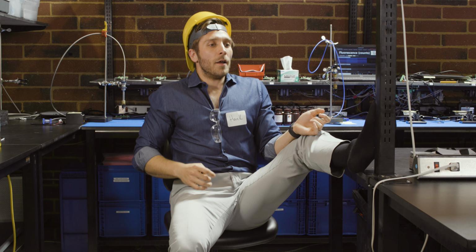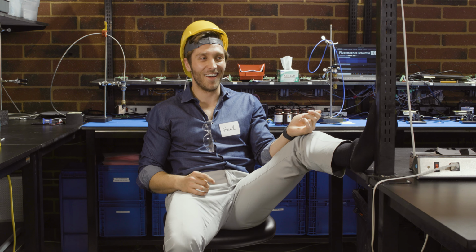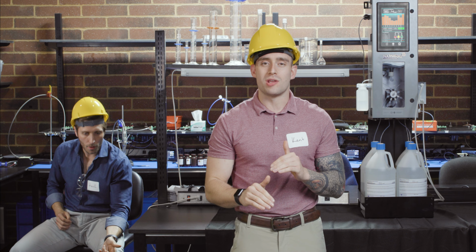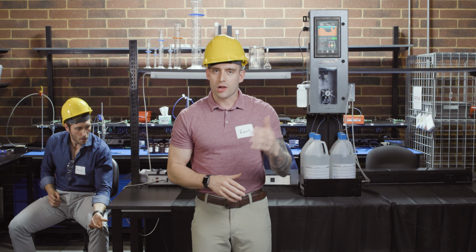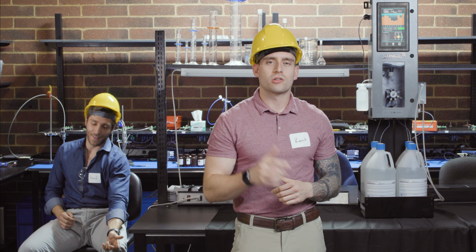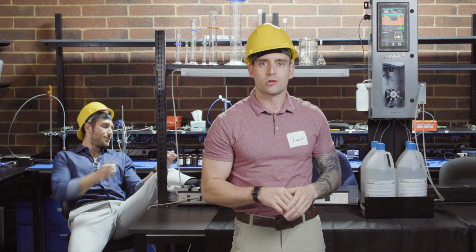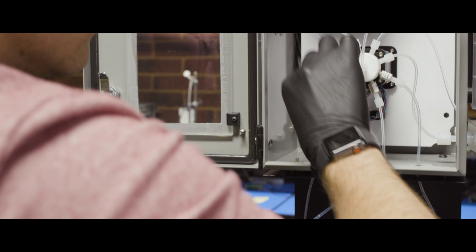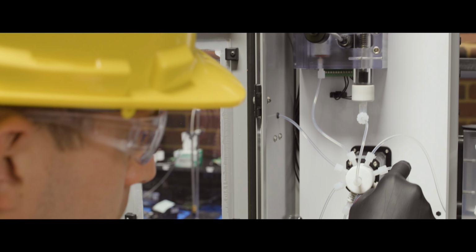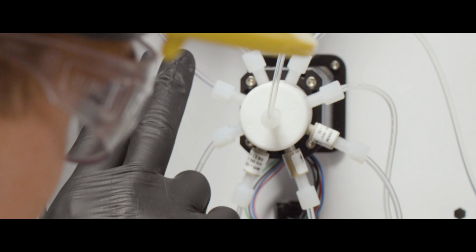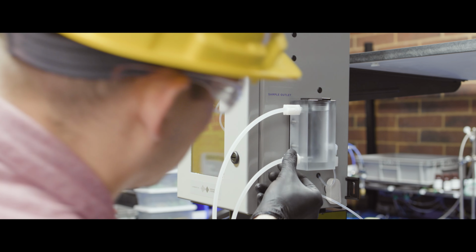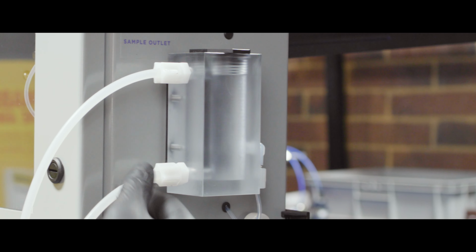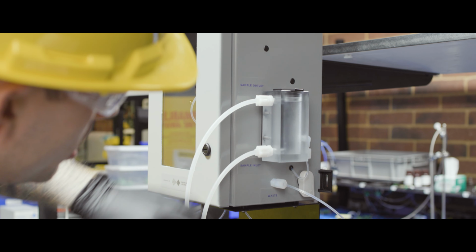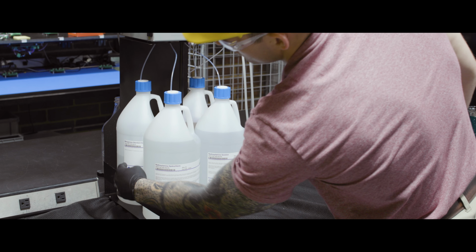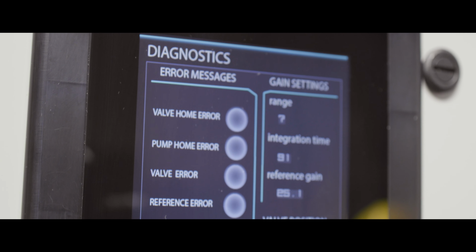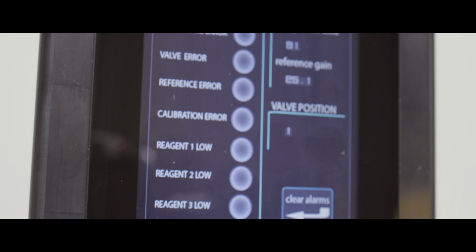Dude, listen. Kenny Ken. So, the Narwhal was designed to ensure that we keep maintenance at a minimum. However, there are a couple of things you're gonna wanna keep your eye on. Let's start with our visual checks to ensure that your analyzer is functioning properly. Step number 1, inspect all tubing for leaks and bubbles, especially around the rotary valve and the sample drain connections. Step number 2, observe the fast loop reservoir for sample. Just make sure she's flowing properly. Step number 3, check your reagent and your standard levels. And step number 4, check for alarms and errors on the Narwhal display.